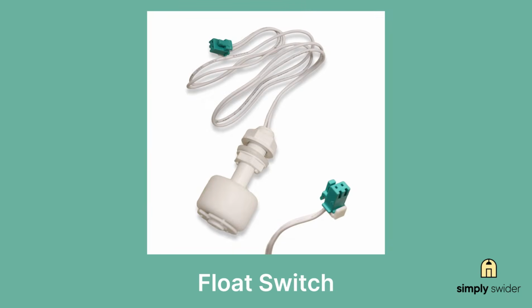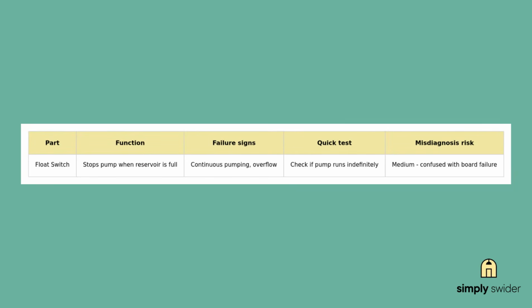The float switch is your overfill protection, and it'll run you about $13 to $15. This is what tells the pump to stop when the reservoir is full. When it sticks, the pump just keeps running until water overflows all over your floor. You can test it with a multimeter to check continuity, but replacement requires getting inside the unit and understanding how the magnetic reed switch system works.